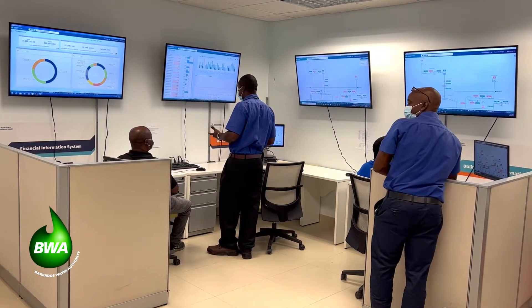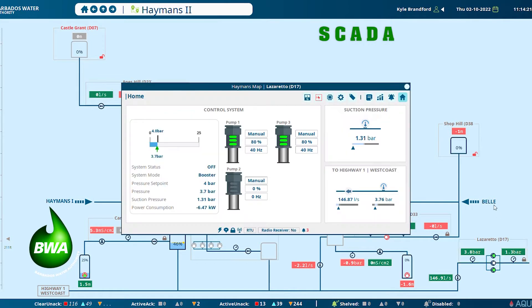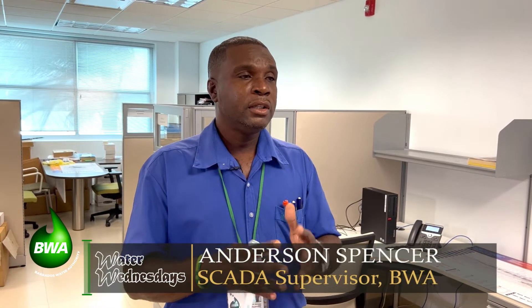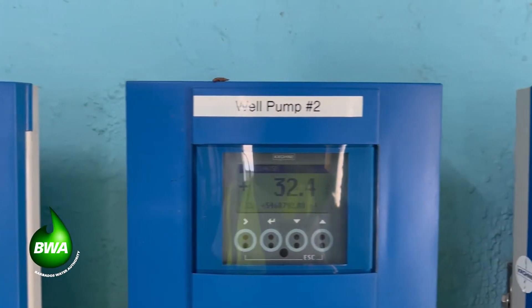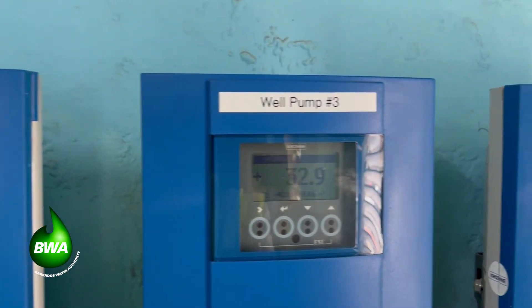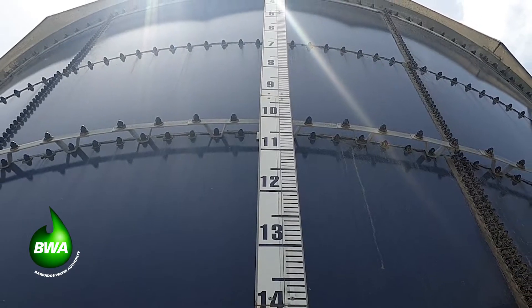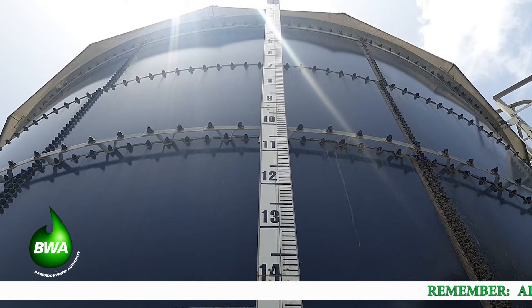The SCADA system is a fully computerized system which enables us to monitor all the potable water stations and the wastewater section of the BWA. With this system, you can see in real-time the operations at these locations, such as the flows — the water that is pumped from the wells and into the water distribution network. There are also the levels in the water reservoirs and tanks, and the salinity, which is the quality of water.